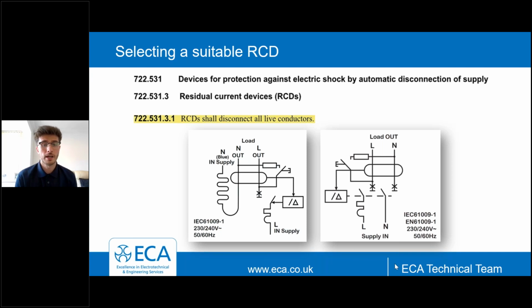Now, the devices shown here are typical images that you would find on RCBOs. So what you might protect, let's say, with a typical RCBO for a single phase circuit. Just to point out, this regulation does also apply to if you had a three-phase charging point, as of course it should disconnect all the line and neutral conductors supplying that equipment.